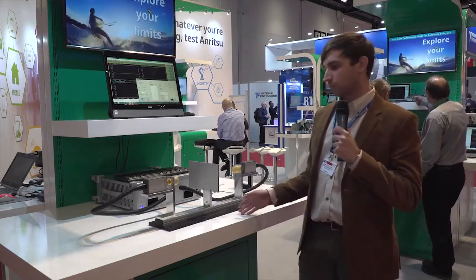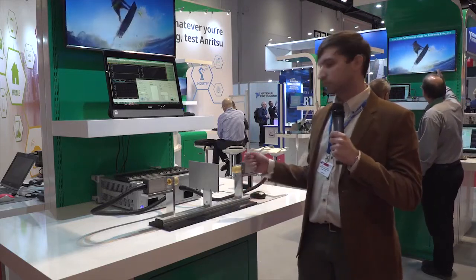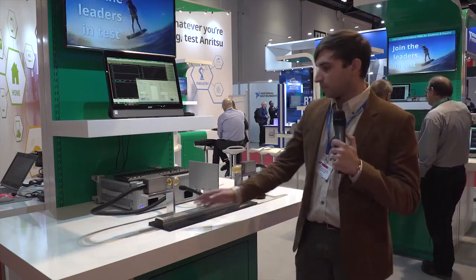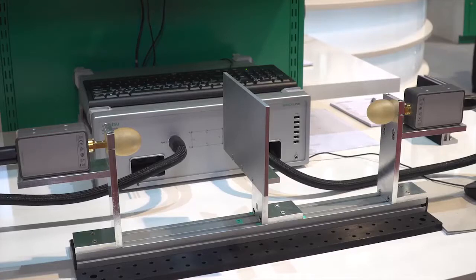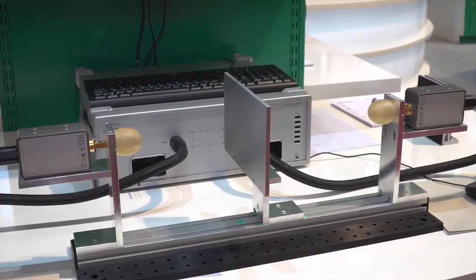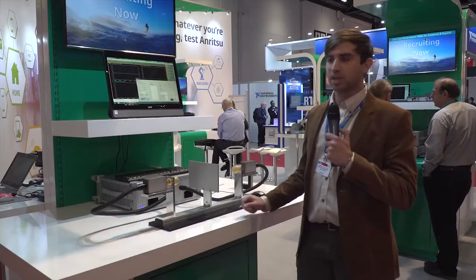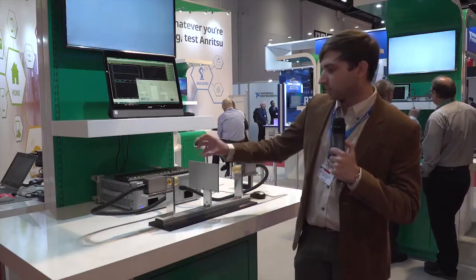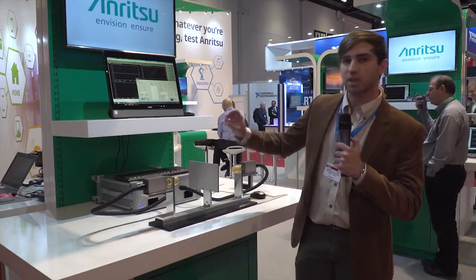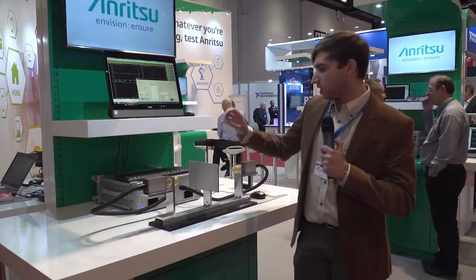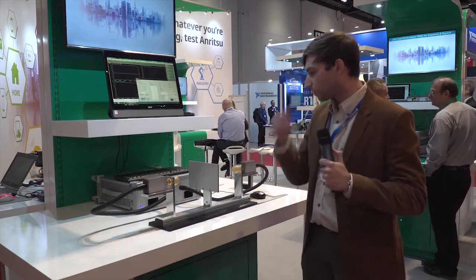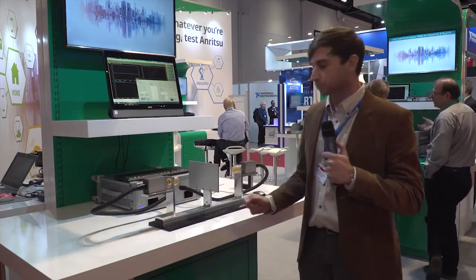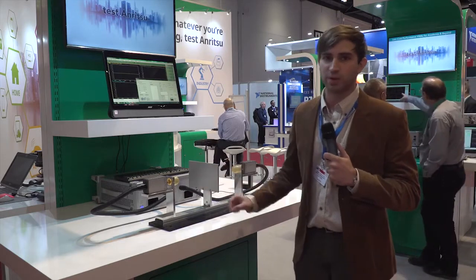I'm Cosme Culotta-Lopez from the RWTH Aachen University in Germany. As Mr. Gerhardes already introduced, it is a cooperation between us, Fraunhofer, and Anritsu. So the setup looks like this. Here we have two very directive antennas that were manufactured by Fraunhofer FHR. The antennas are dielectric drop antennas designed by Professor Paul in Bochum. The concept is that this dielectric drop models the beam and shapes it to be very directive. The beam has a spot of around 28 millimeters, which ensures that the transmission is almost complete with no losses in the middle, except for the loss in the dielectric that we will calibrate out.